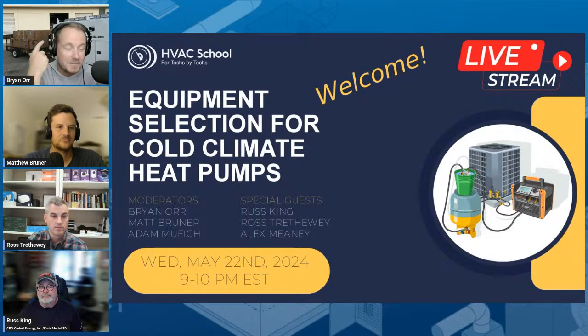And to what Matt's saying, it's amazing how many HVAC technicians and contractors don't recognize that even in markets like Central Florida, our heating load is still greater than our cooling load, right? When you're talking about peak, regardless of whether you're looking at a design day or not, but you certainly have moments where your heating load is greater, because you just look at the delta between your desired indoor temperature and your minimum outdoor temperature is always going to be much greater. And again, when I say always, obviously there are markets that's not true, but even in Central Florida, we will have a 25-degree day on occasion. And we still have a desired indoor temperature in the mid to high 60s, which is a significant delta. So it's these kind of basic concepts that I think we have to drive home first and foremost.